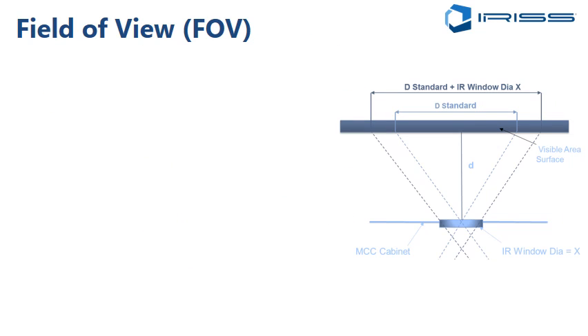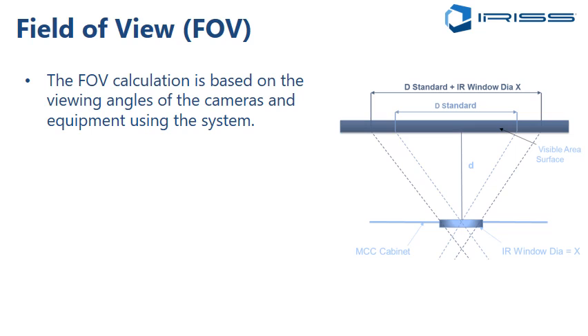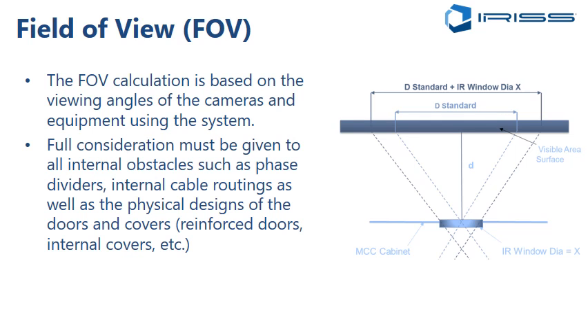So first, let's look at field of view. Now, the field of view calculation is based on the viewing angles of the cameras and the equipment used in the window systems that you have in place. So full consideration must be given to all internal obstacles, such as phase dividers, internal cable routings, as well as the physical designs of the doors and covers. Some have reinforced or internal covers, etc.